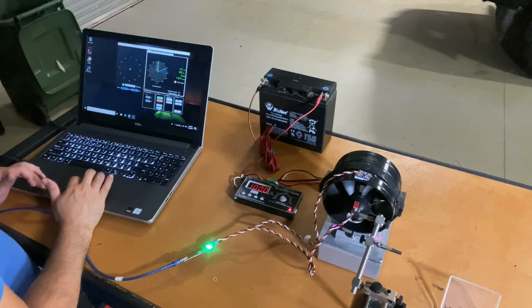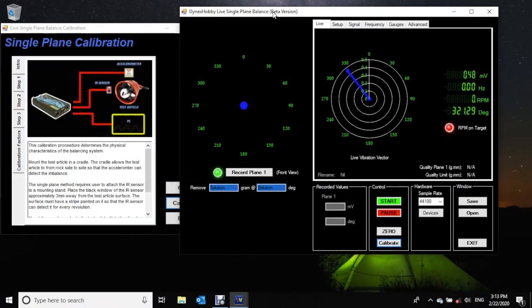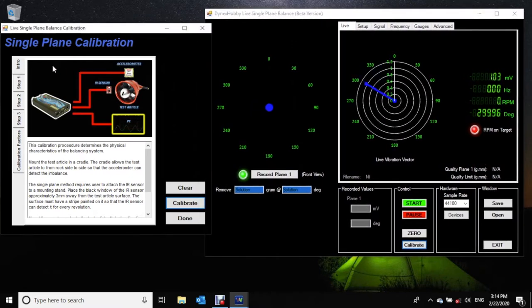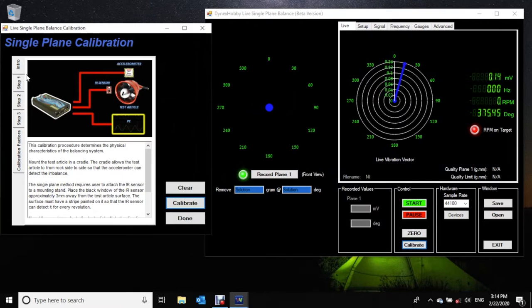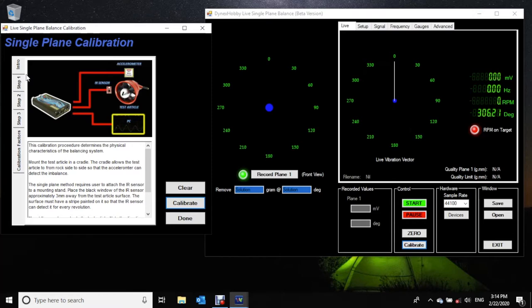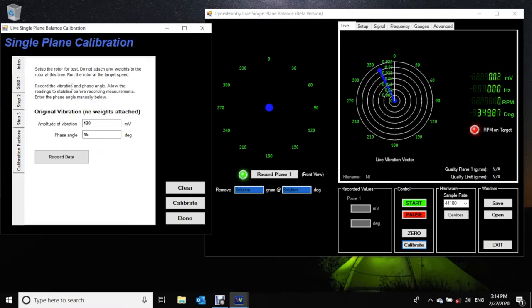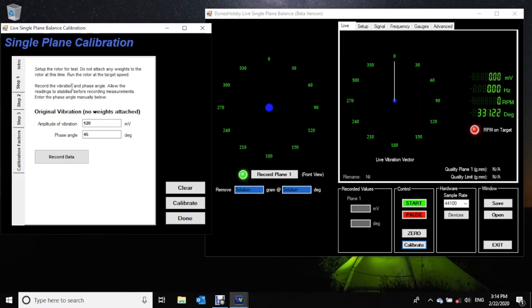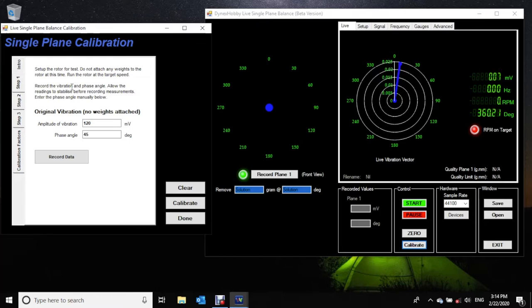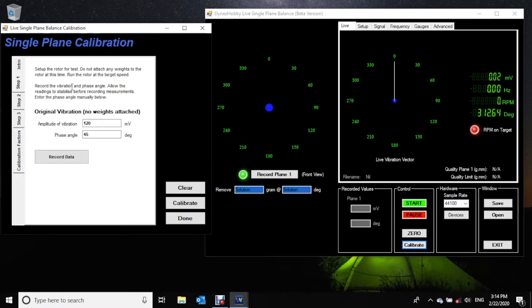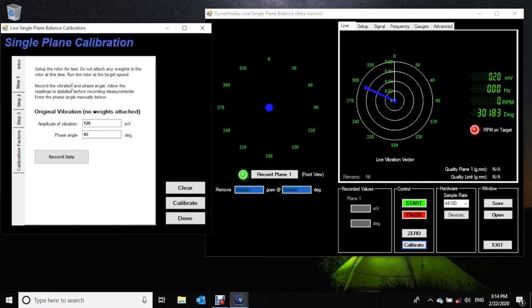Getting started, there's a button called Calibrate on the center bottom of the console, and another window will pop up, called the single plane calibration, and it's broken into steps on tabs located on the side of the window. There's an introduction, which basically identifies your setup and how to perform the calibration. So we'll progress into step 1, and step 1 says to set up the rotor for the tests, and what we want to do is run the EDF at our test speed and measure the existing vibrational level without any weights or anything applied to the EDF.